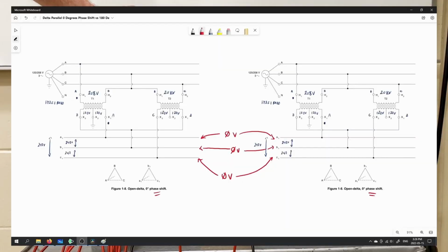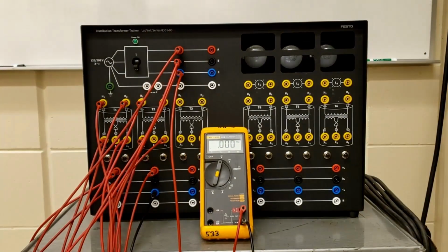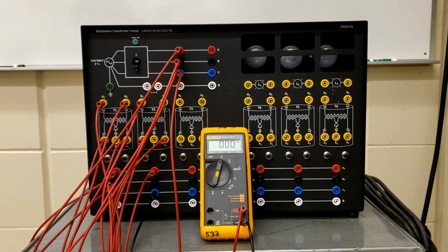Okay, then the next one says open delta 0 degrees phase shift versus open delta 180 degrees phase shift. Okay, so repeat the circuit shown in 1-8 using transformers T4, T5, lines A2, B2, and C2. Connect bushings X2 to the ground terminal. Okay, so let's do this identical wiring on the other side here. Okay, so this is where we're gonna compare the two open deltas, right?